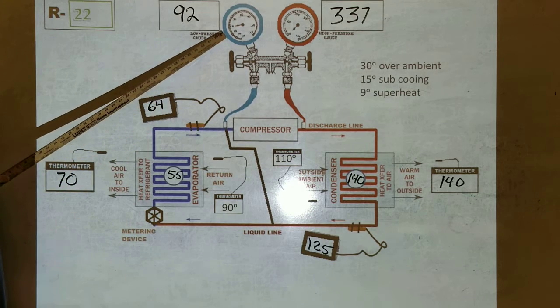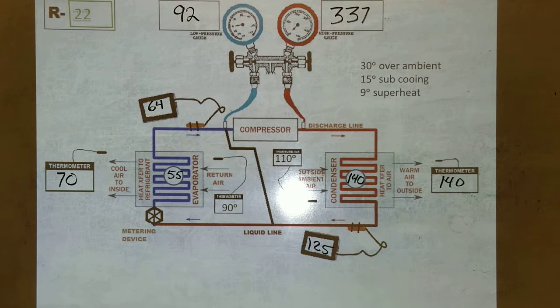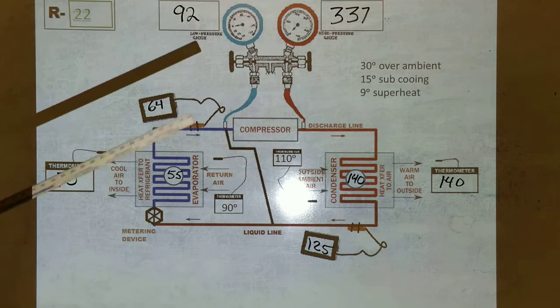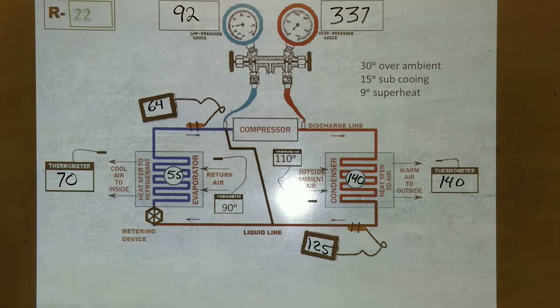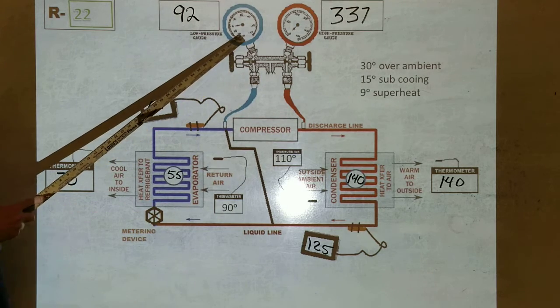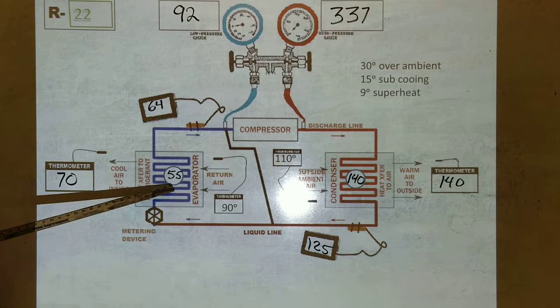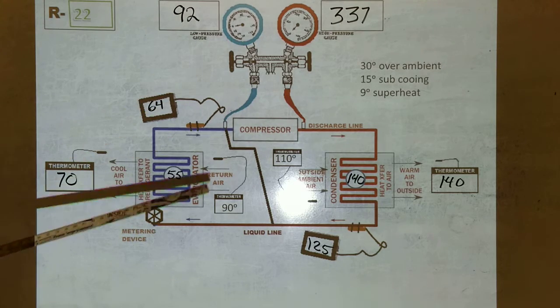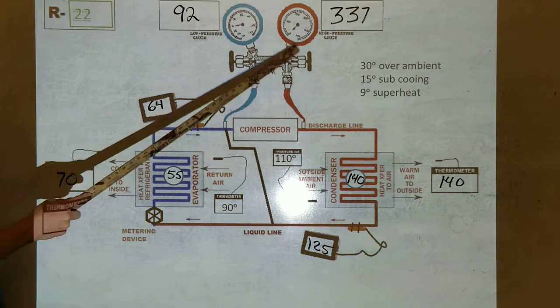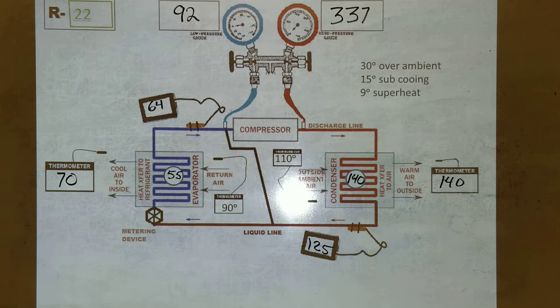So, the pressure, I don't care what the pressure is, and you shouldn't care either. It's no big deal. Pressure doesn't mean nothing to me, because the pressure's going to change. What I'm concerned about is that temperature right there. That pressure's going to tell me what that temperature is, so the pressure gauges are there just to give us the temperature. That's all they're for, so it's no big deal.